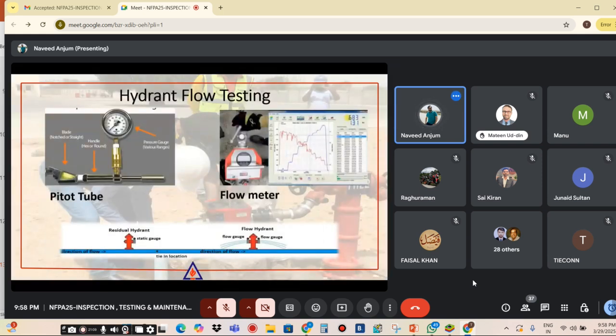Then hydrant flow testing. Someone also at the start of the presentation said that they are performing this type of test, so you can see which system, how you can perform it, and whether it is okay or not. Basically, in hydrant flow testing we have to check our hydrant flow. We can use a pitot tube for this, and we can also use a flow meter. With a pitot tube we convert velocity to flow, and a flow meter will just show you the flow of the system. This is also mandatory, because if you test your hydrant system and it is meeting the design requirement, then in case of emergency it will help you to extinguish the fire easily.